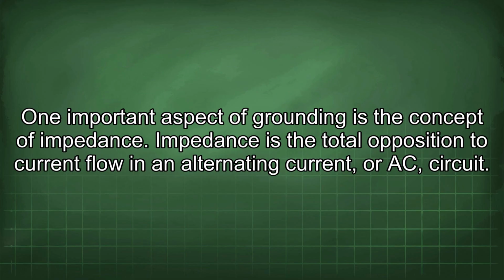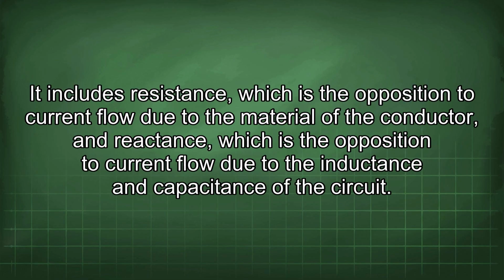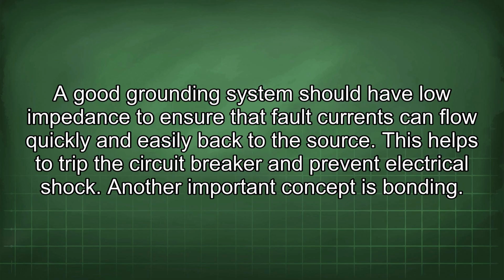One important aspect of grounding is the concept of impedance. Impedance is the total opposition to current flow in an alternating current, or AC, circuit. It includes resistance, which is the opposition to current flow due to the material of the conductor, and reactance, which is the opposition to current flow due to the inductance and capacitance of the circuit. A good grounding system should have low impedance to ensure that fault currents can flow quickly and easily back to the source. This helps to trip the circuit breaker and prevent electrical shock.